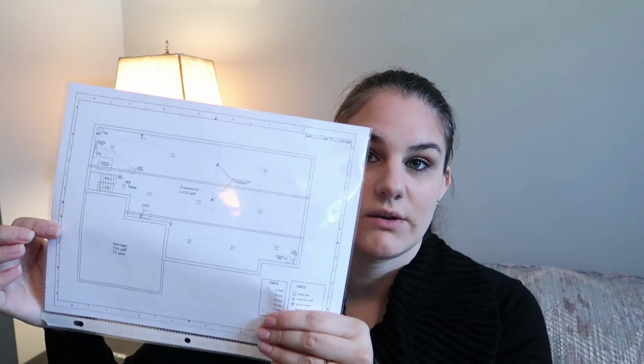You want 2 switches controlling 1 light in the center, so we have a lot of those. Then you have to figure out your basement electrical. Usually it's a lot of hardwire stuff, your HRV, which is a heat recovery ventilator, and your furnace, sump pump, that type of thing - usually those will all have their own circuits. And don't forget about your outside electrical. If you want outlets or light fixtures on the outside, you have to do those circuits as well.